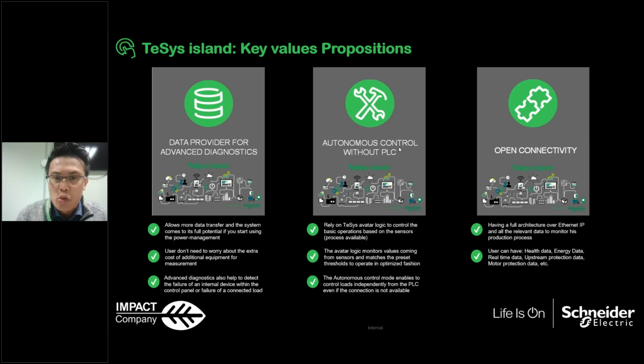The fifth is autonomous control without a PLC. This is something very interesting that we will talk more about later. So within the TeSys island, you can actually set autonomous control without the PLC. Let's say for typical pump applications, for a basic application, if the water in the tank is lower than a certain level, the motor should be kicked off. And if the water level is higher than a certain level, the motor should be stopped.